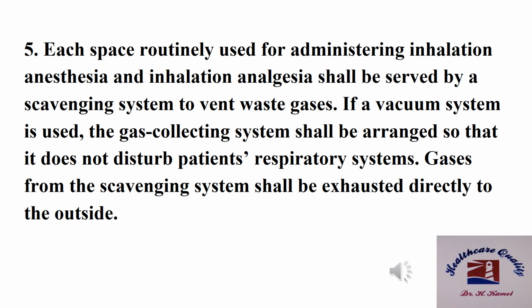Number 5, each space routinely used for administering inhalation anesthesia and inhalation analgesia shall be served by scavenging system to vent waste gases. If a vacuum system is used, the gas collecting system shall be arranged so that it doesn't disturb patients' respiratory systems. Gases from the scavenging system shall be exhausted directly to the outside.